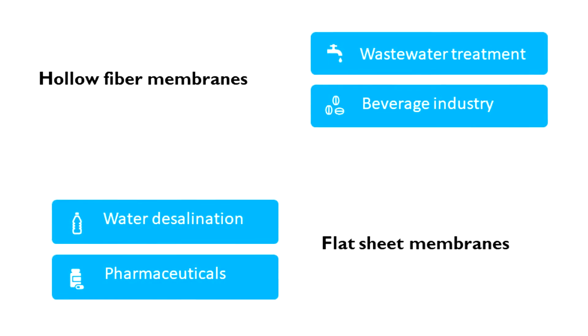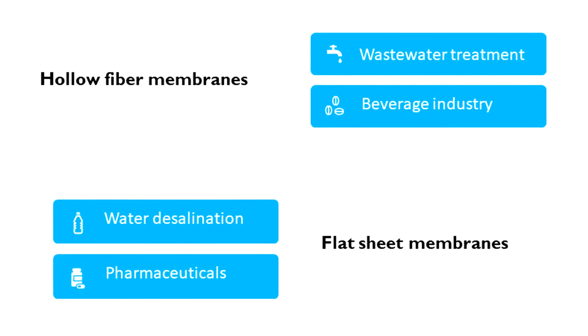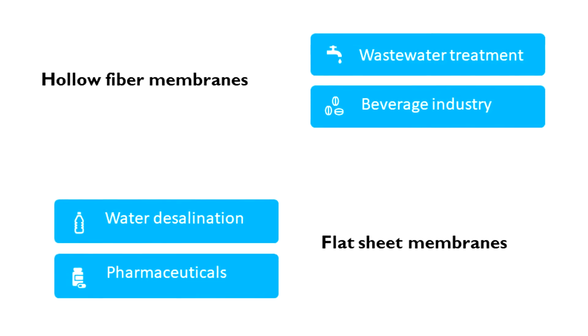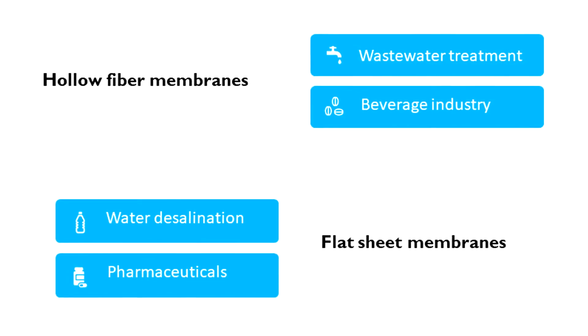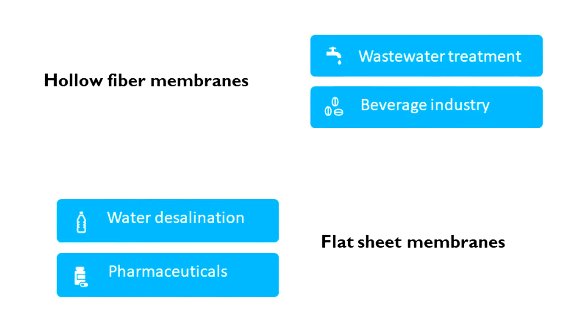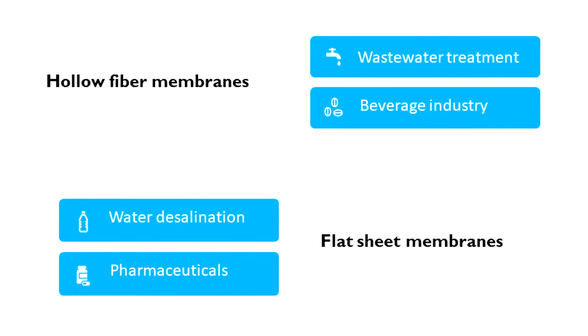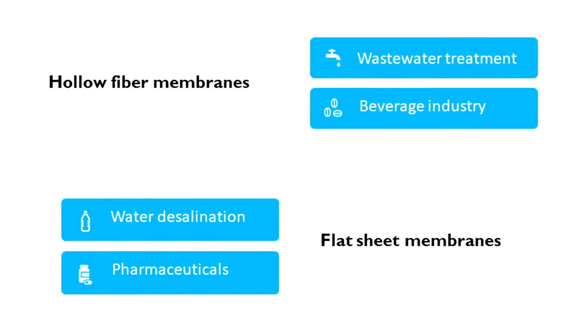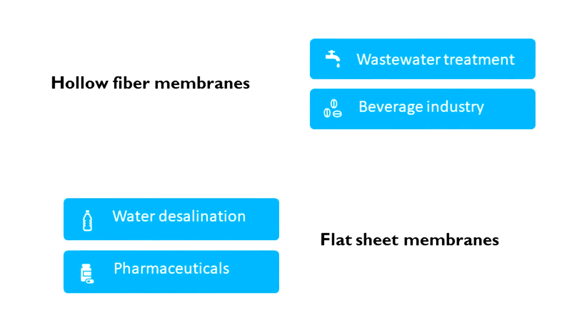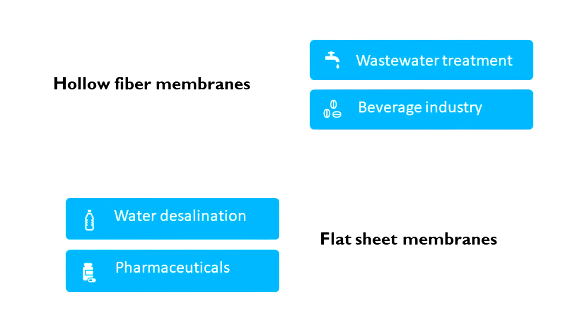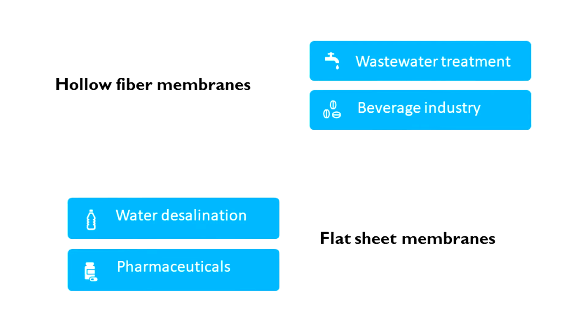Hollow fiber membranes can generally be cleaned by reversing the flow direction, removing the particles from the membrane surface. Flat sheet membranes are mainly used in NF and RO applications. Typical applications are water desalination for the production of drinking water, production of alcohol-free beer, and the separation of pharmaceuticals from the production process. These types of membranes are generally cleaned by treatment with dedicated cleaning agents.